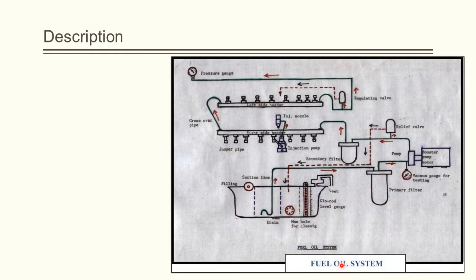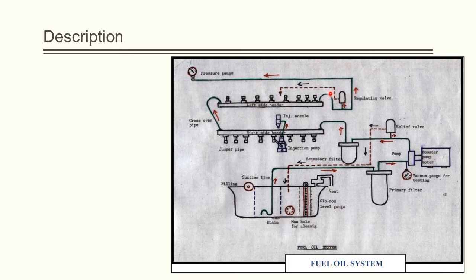The fuel booster pump or transfer pump is switched on and starts sucking oil from the fuel tank, which is filtered through the primary filter. Because of variable consumption by the engine, the delivery pressure of the pump may rise, increasing load on the pump and its drive motor. When the rate of consumption of fuel by the engine is low, the relief valve ensures safety of components by bypassing the excess pressure back to the tank. The oil then passes through the paper type secondary filter and proceeds to the right side of the fuel header, which is connected to the eight fuel injection pumps on the right bank of the engine.